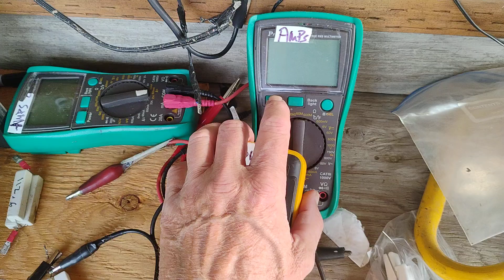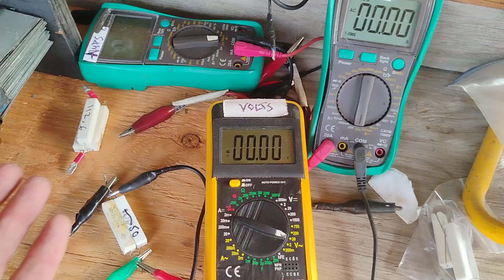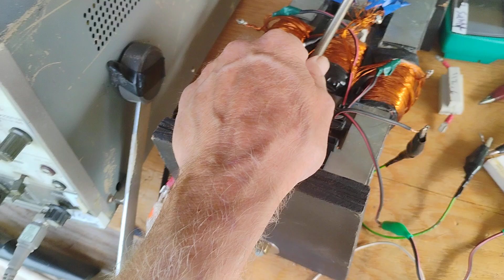But where everybody goes wrong, or maybe right, is they measure the amps in and the volts in, and say, oh, this is the watts, but they don't include the power factor. And power factor is only something in AC that you can mess with. So the AC watts input is volts times amps times PF, power factor. If it's 90 degrees, the power factor is 0, so volts times amps times 0 equals 0. Isn't that nice?